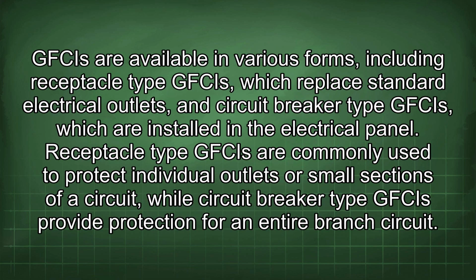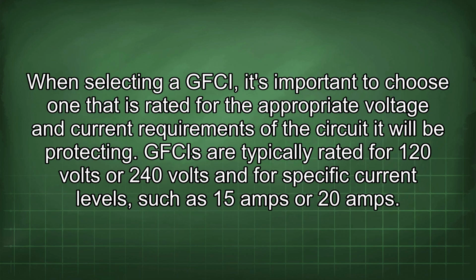GFCIs are available in various forms, including receptacle-type GFCIs, which replace standard electrical outlets, and circuit breaker-type GFCIs, which are installed in the electrical panel. Receptacle-type GFCIs are commonly used to protect individual outlets or small sections of a circuit, while circuit breaker-type GFCIs provide protection for an entire branch circuit. When selecting a GFCI, it's important to choose one that is rated for the appropriate voltage and current requirements of the circuit it will be protecting.